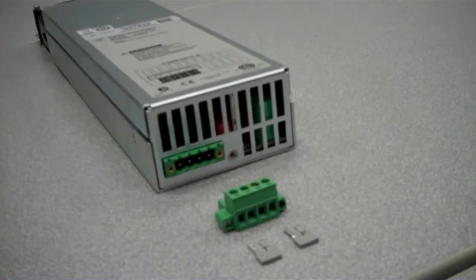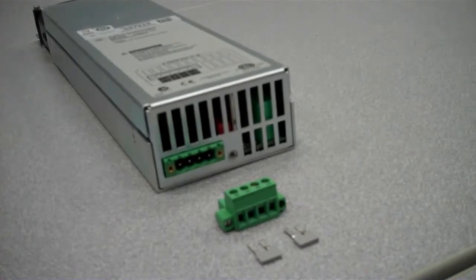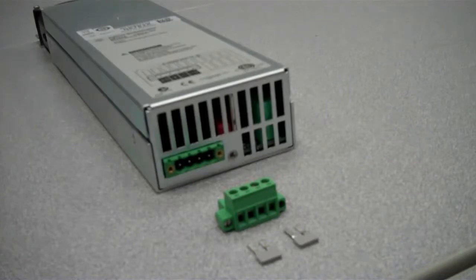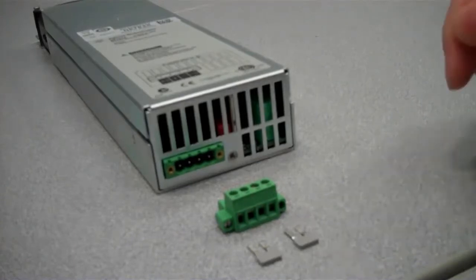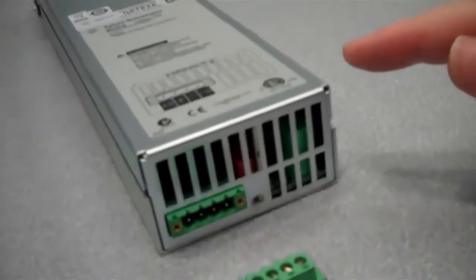All the modules on the output label on the top have the legend of how to wire your connector. This little picture here shows you how to connect the wires up on your output connector. If you ever want to look at how to connect it correctly, always refer to this label.